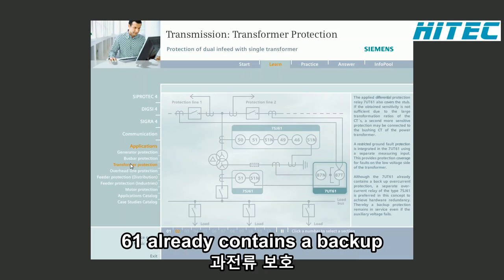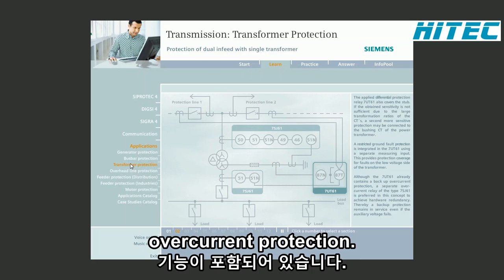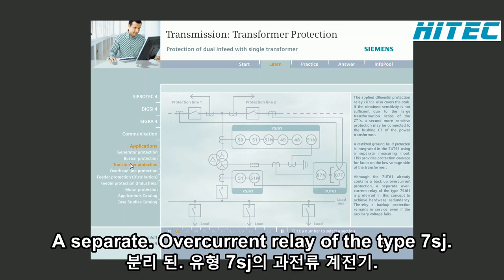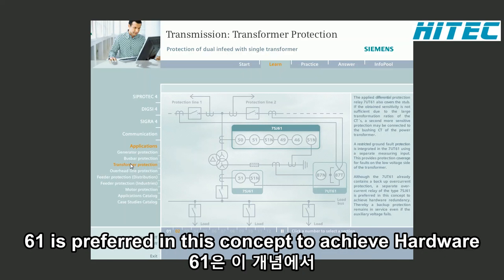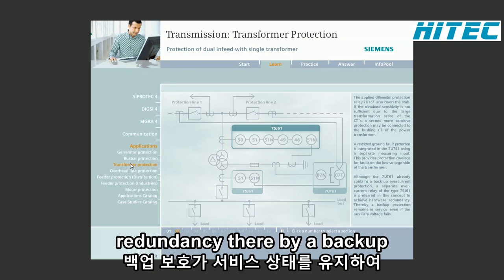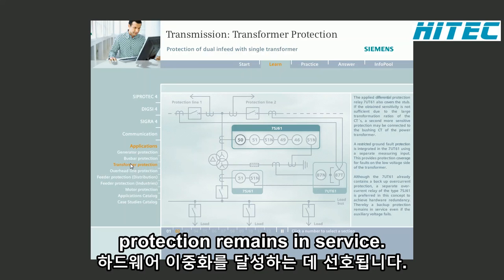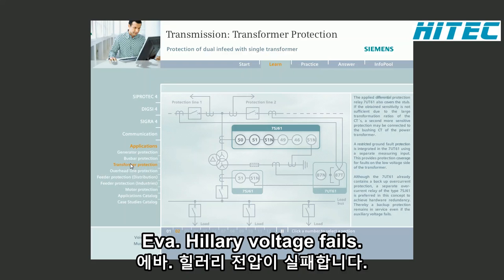Although the 7UT61 already contains a backup overcurrent protection, a separate overcurrent relay of the type 7SJ61 is preferred in this concept to achieve hardware redundancy. Thereby, a backup protection remains in service even if the auxiliary voltage fails.